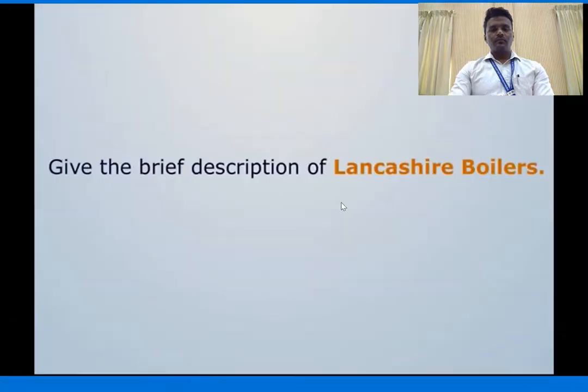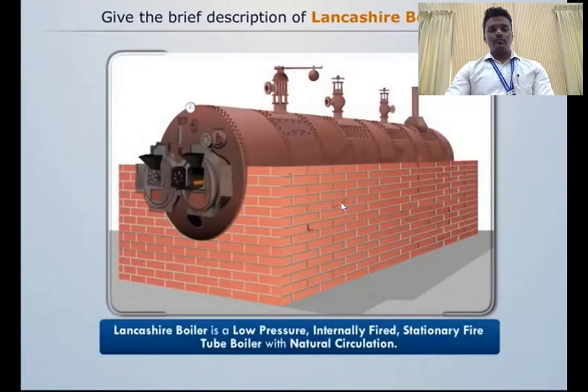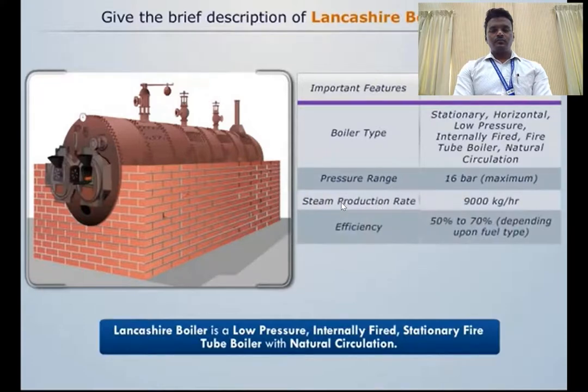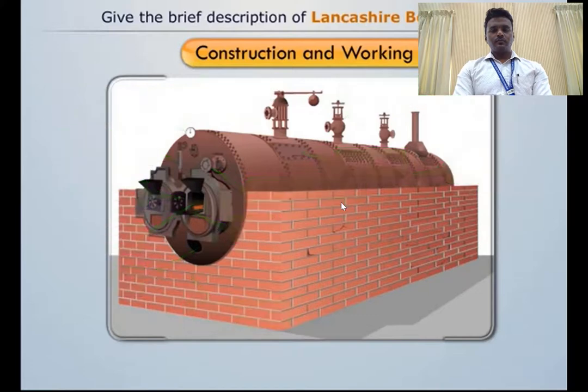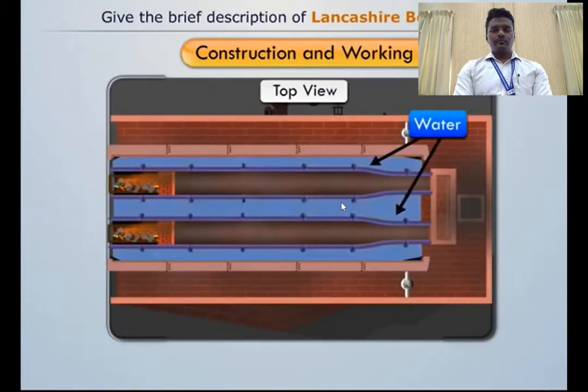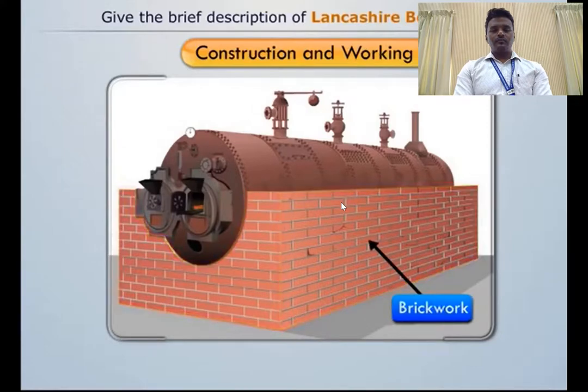Lancashire boiler is a low-pressure, internally fired, stationary fire tube boiler with natural circulation. Its pressure range, steam production rate, and efficiency are notable. Lancashire boiler consists of a horizontal cylindrical shell filled with water surrounding two large fire tubes. The cylindrical shell is placed over brickwork, which creates several channels for the flow of hot flue gases.